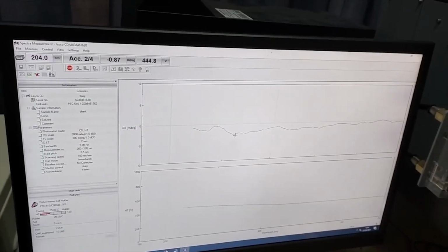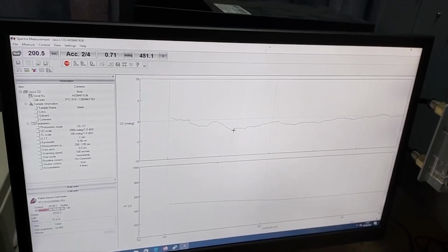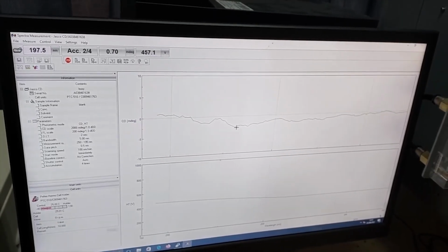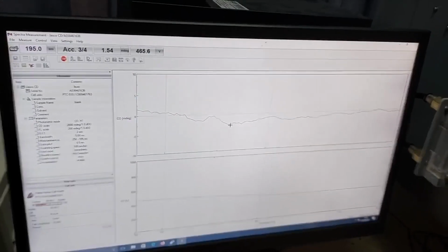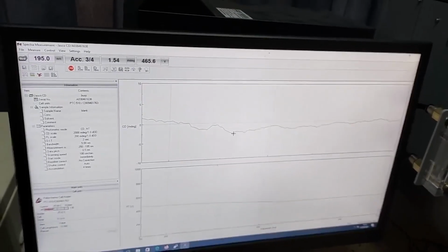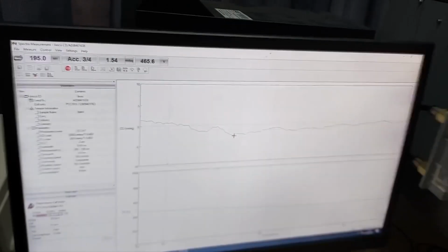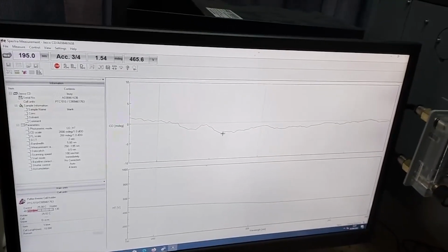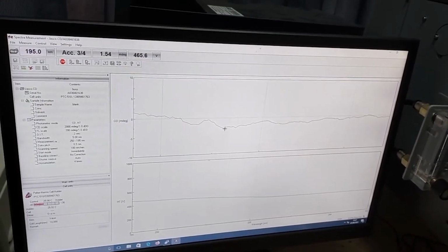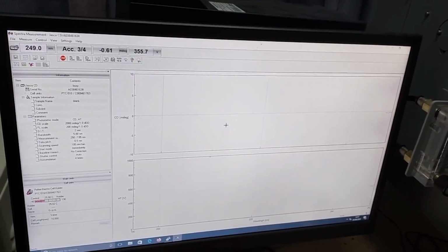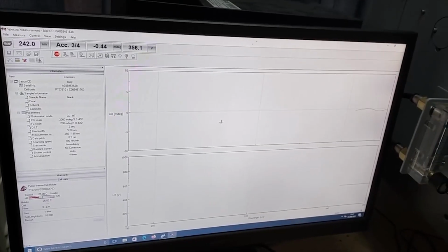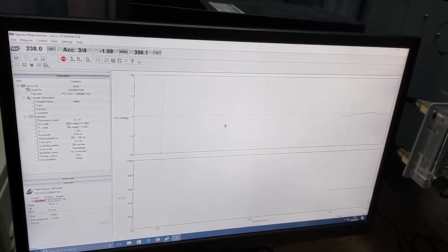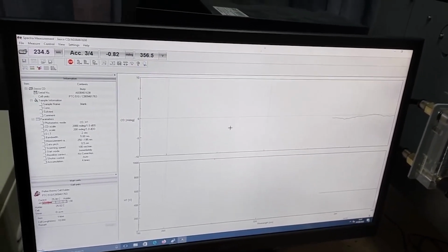As the sample absorbs photons, fewer photons will reach the detector. So a higher voltage is applied to the detector to get more secondary electrons from the PMT. Essentially, your light gets extinguished by your sample and a higher voltage is applied. So when the absorbance of the sample becomes too high, very few photons reach the detector.